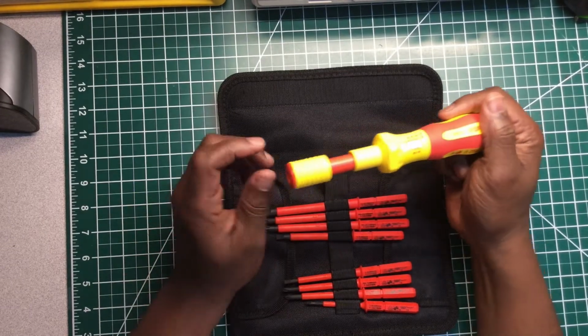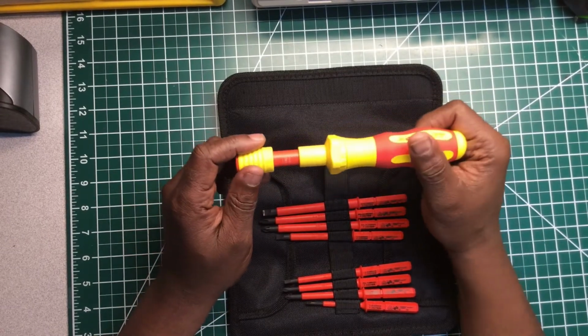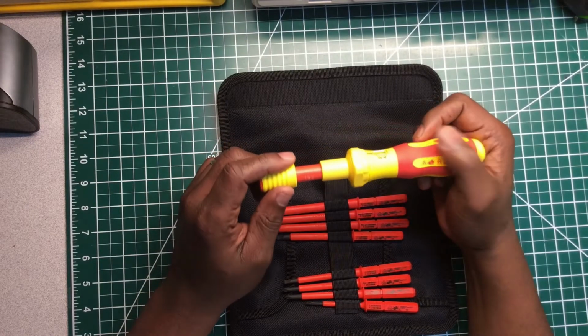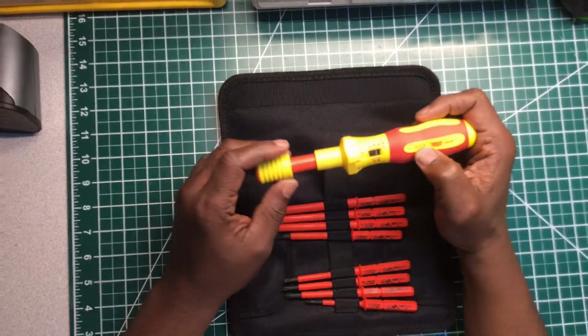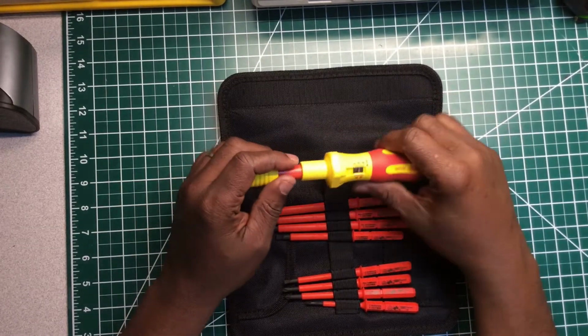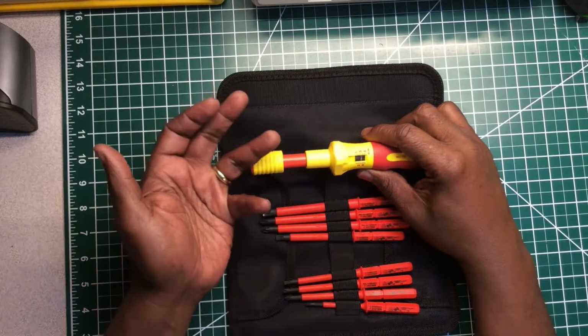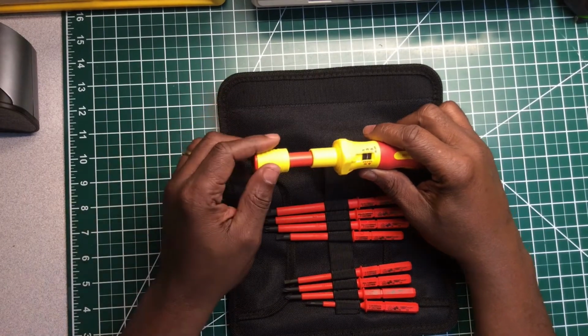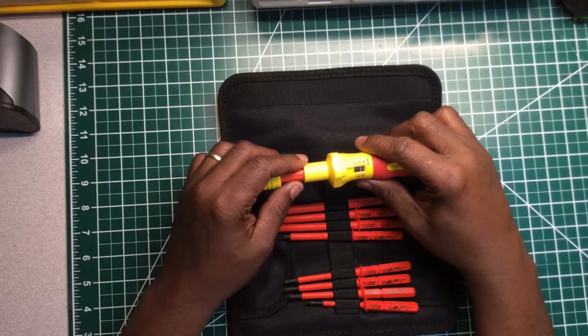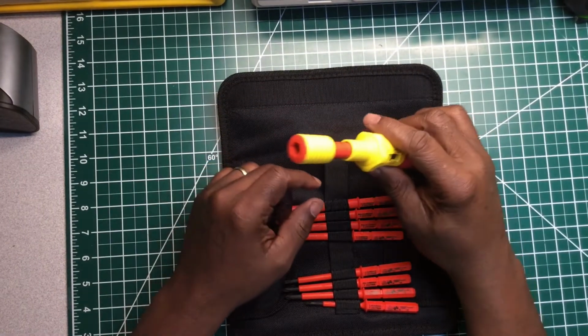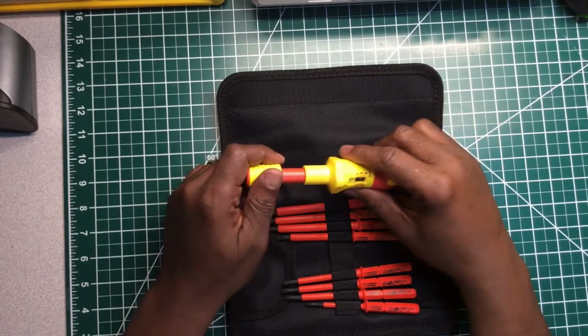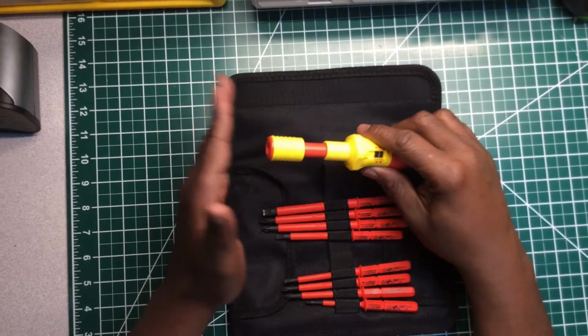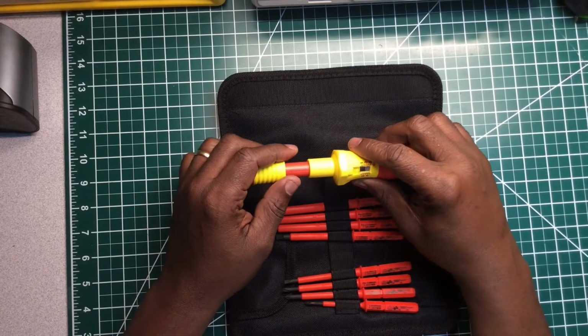I recommend having torque screwdrivers if you can, both a non-insulated one and an insulated one. It's not only my recommendation, it's a requirement by several electrical codes. I know the NEC recommends it, and the Canadian electrical code recommends it, and there are probably several others around the world that recommend that your electrical connections be torqued to a certain value recommended by the manufacturer of that device.